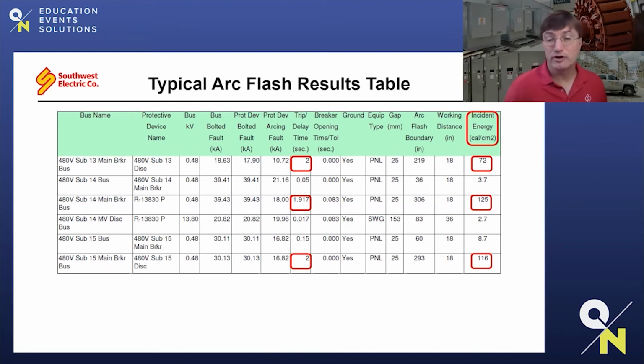You can tell that the other clearing times are relatively small, usually within 170 milliseconds was the highest. 17 milliseconds. Therefore, those clearance times are very small, and as a result, the incident energy is also very small. Now I want you to recognize the voltage level of these particular buses. They're all at the 480 volt level.